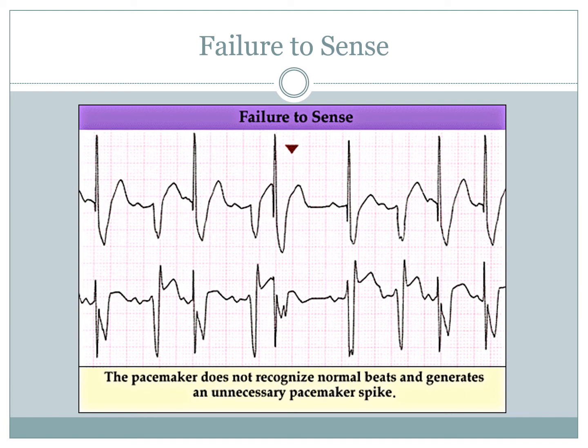But then, what is this? What's going on here? There was no reason for that pacer spike that's close to the arrow. It didn't even sense whether or not the normal beat was going to occur. So it threw an inappropriate spike. The pacemaker does not recognize the normal beats and generates an unnecessary pacemaker spike.